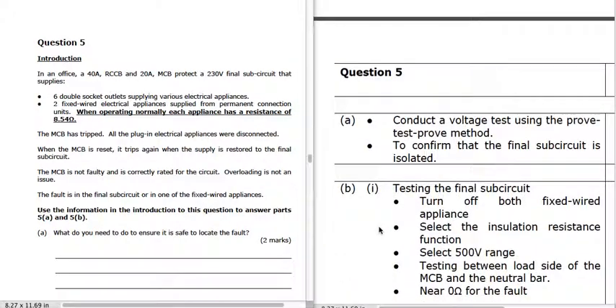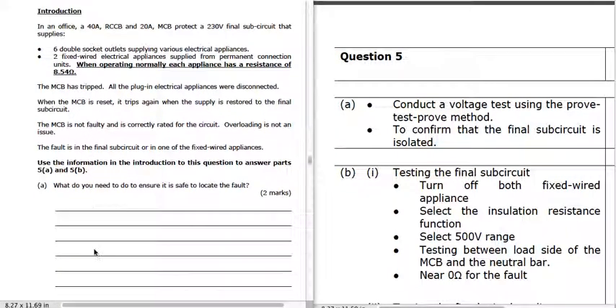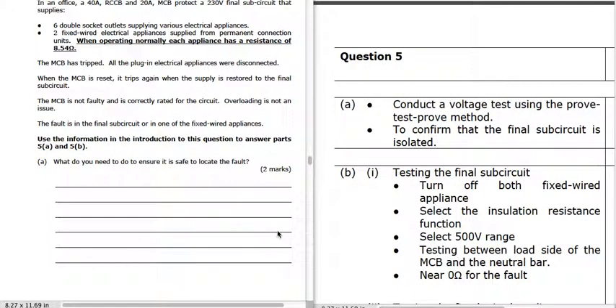Question 5: we've got an office with a 40-amp RCCB and 20-amp MCB protecting the 230-volt sub-circuit with six double socket outlets and two fixed-wire electrical appliances. Each appliance has a normal resistance of 8.54 Ω. The MCB keeps tripping but is not faulty. To ensure it's safe to locate the fault, we use prove-test-prove to confirm that the final sub-circuit is isolated.